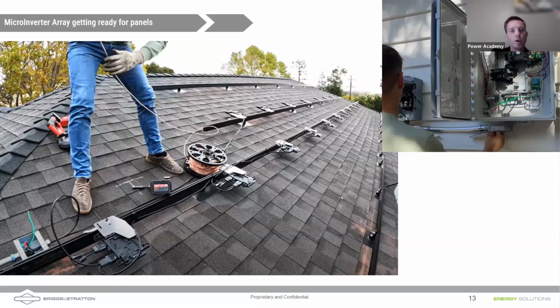Those microinverters are going to be all paralleled up at 240 volts AC with the trunk cable. And those will be combined into strings, but slightly different strings from the DC types of strings, right? Strings of panels that were paralleled. And so those currents will add up. And then you'll have a combiner box typically down on the side of the house. So what you're looking at here, I see a conduit drop coming down, and then those strings coming into, looks like 2 inputs, 2 strings here. And then this is the Enphase combiner box, and this is an AC disconnect, it looks like here. And then that power will be sent from that AC disconnect into the load center of the house. If there's excess power, the excess power will flow back to the grid.